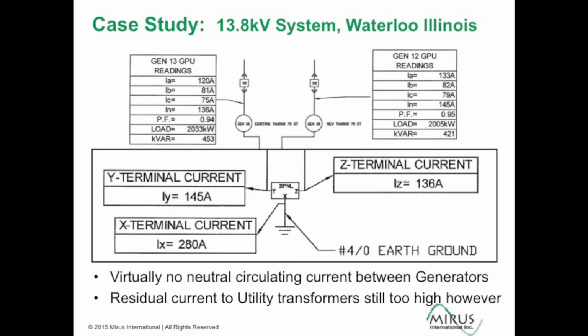So we installed a DPNL in the return neutral current here, and after the installation, when they went back and measured it, you could see there was still a significant amount of current. This is the current from one generator, and then the current from this second generator. So 145 amps on one, 136 amps on the other. And there was still current going through to ground. If we total the 145 and the 136, we get 281 amps.